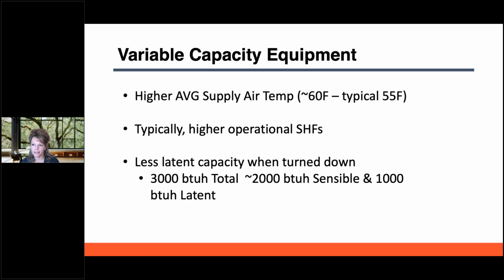So variable capacity equipment, we get this all the time. Well, I'm using variable capacity, so I'm getting the dehumidification that I need. They typically have higher than average supply air temps. So again, those coils aren't getting as cold. Their sensible heat factors are higher, meaning they're not removing as much moisture. And still, 2/3 of the BTUs are focused on the sensible, and 1/3 is focused on the latent, and you still have to have a load. You've got to have a load for the AC to be running.